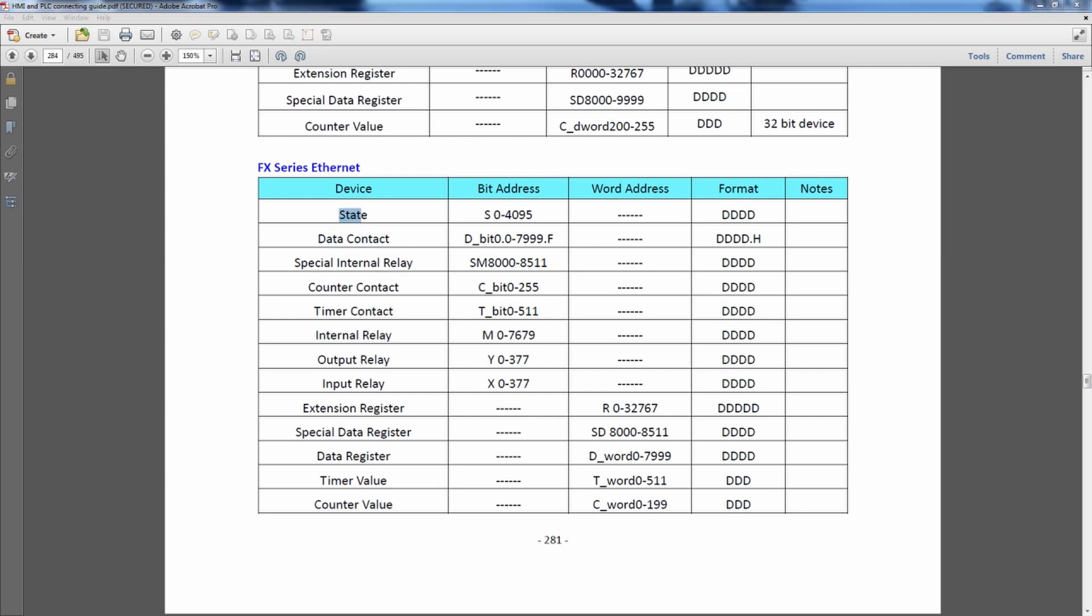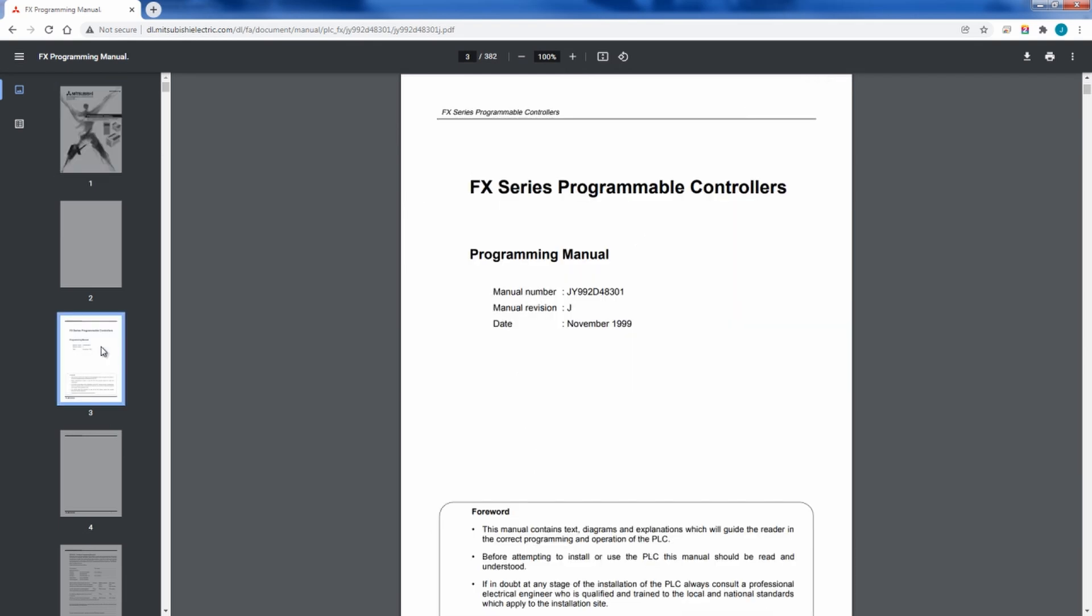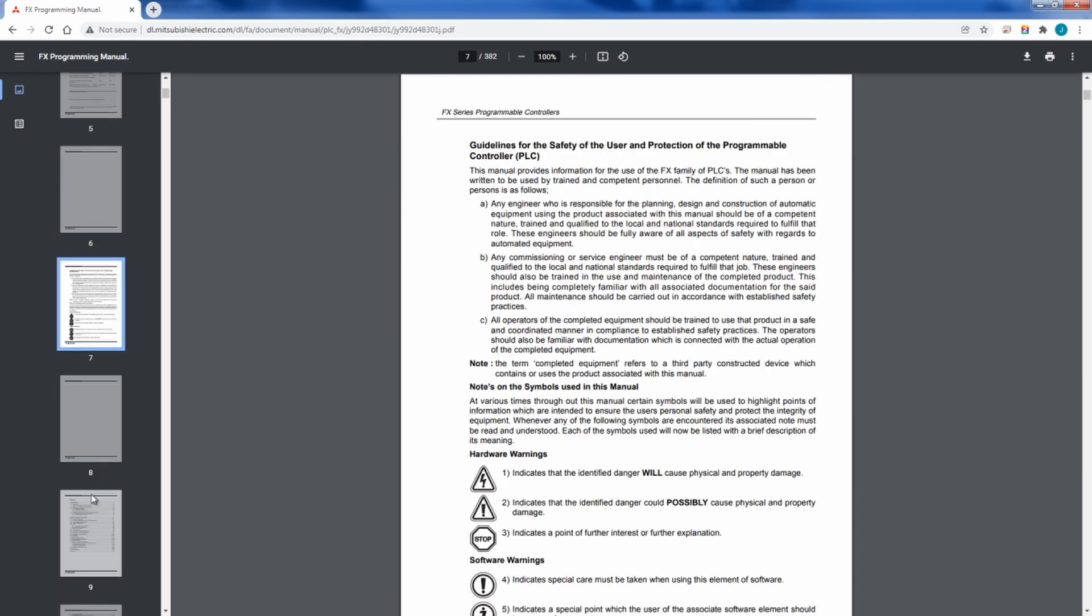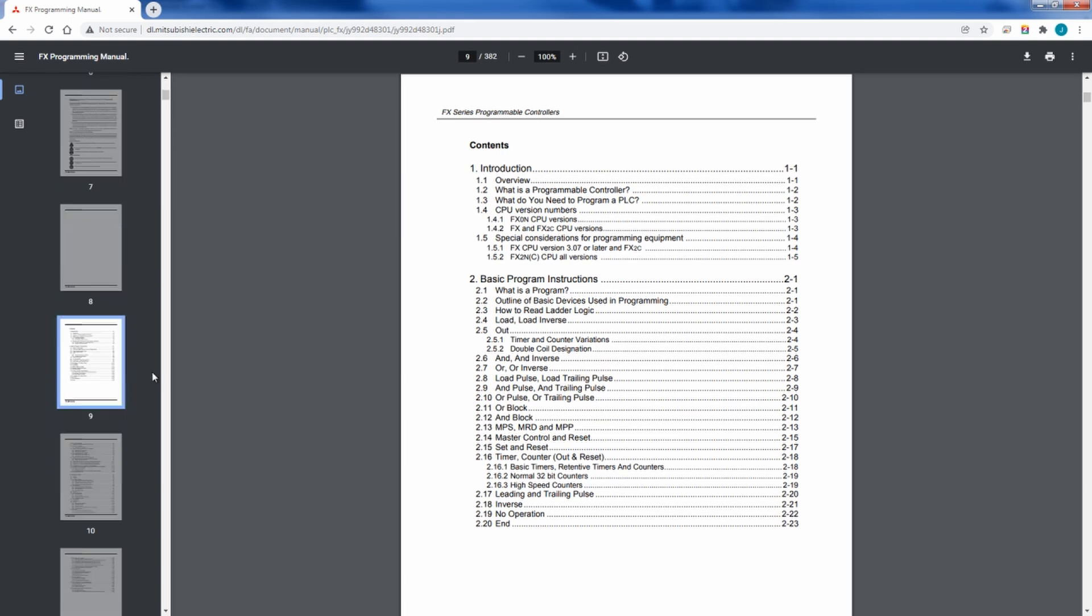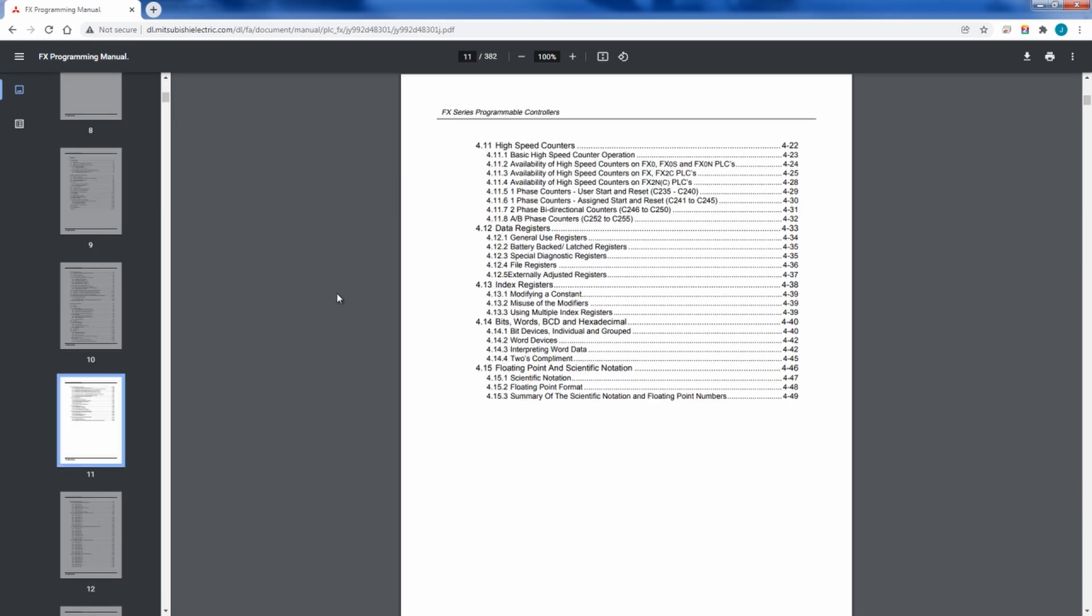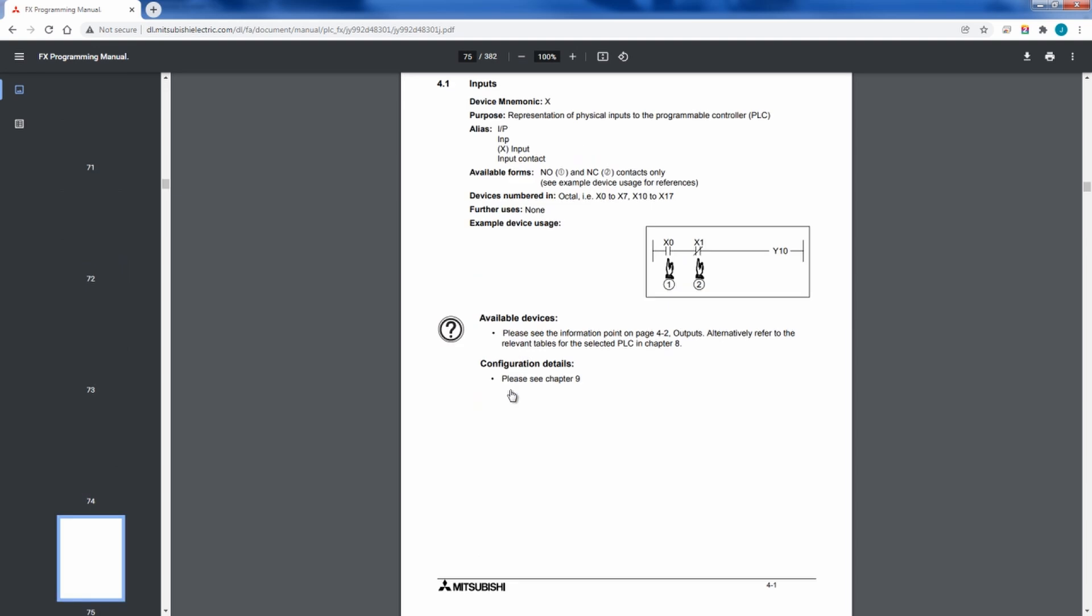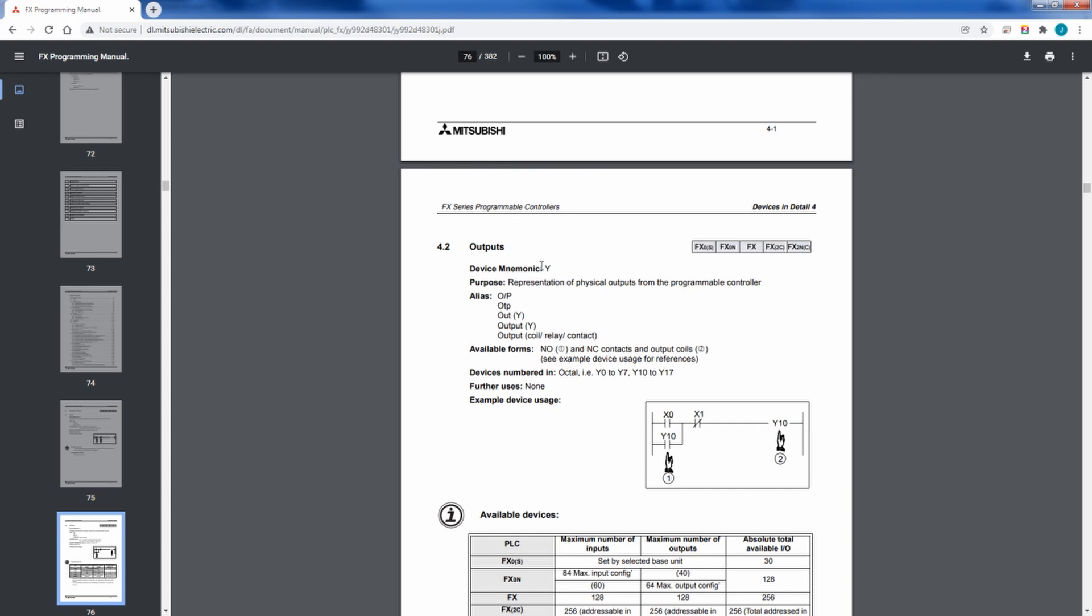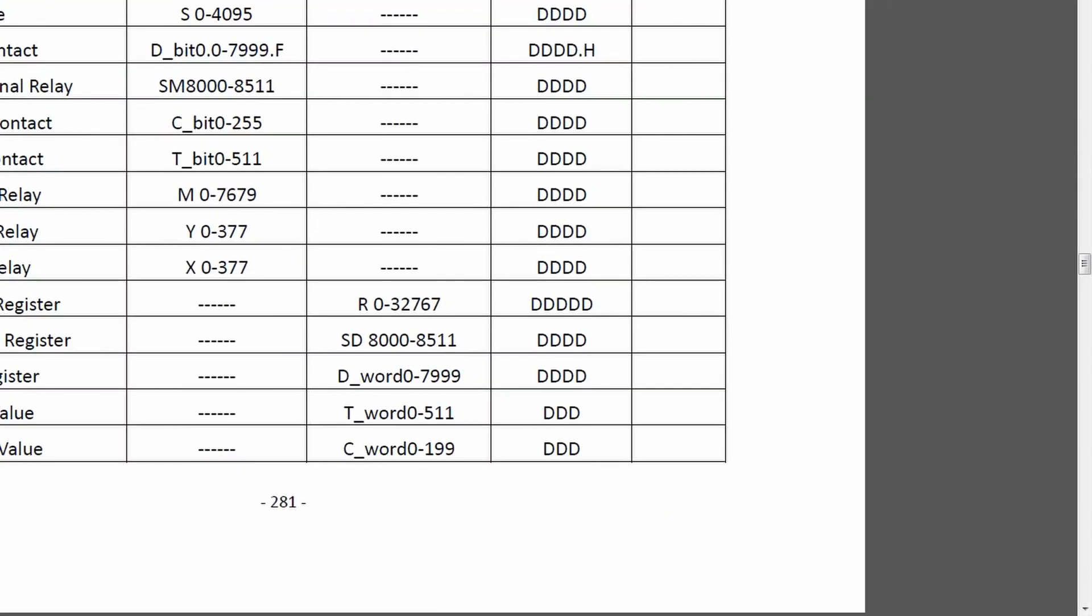Using this communication connection guide, I know where my data addresses will exist for whichever device I'm using. And I can always double check that by actually going to the programming manual. If I go to the programming manual and I keep scrolling through and I look for the programming instructions, what I want to look at is data registers inputs. If I go to inputs, right here, it says that the device mnemonic is X. If I scroll down, outputs, the device mnemonic is Y. And what we said on the communication guide, inputs X, outputs Y.